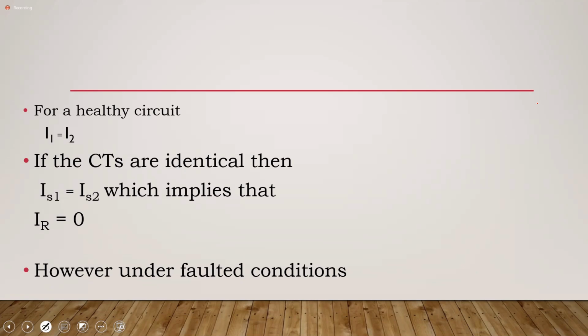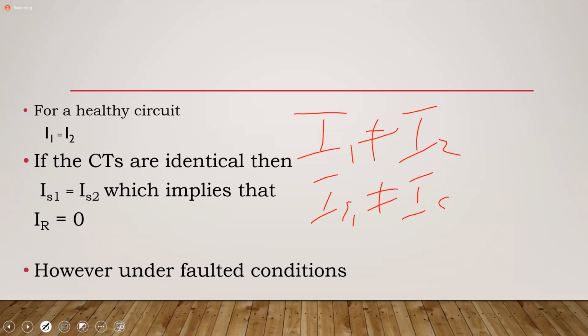However, if we have a fault on the system, right? If there's a fault on the system, then the I1 would not be equal to I2, yes? And so IS1 would not be equal to IS2. And so IR would be greater than 0. Okay? And if IR is greater than 0 and it passes a certain threshold, then you have operation.